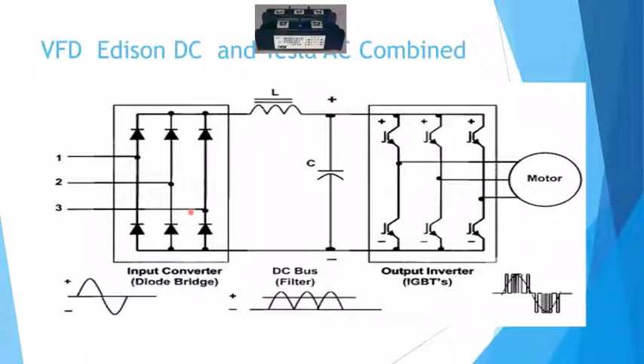Then what came about is the VFD technology. I was trained in this in the 80s very heavily. And what it's doing is basically have phase 1, phase 2, phase 3. You got your sine phase power here. It goes through diodes, and the first thing we're doing is building DC, which is what a lot of the original variable speed was, DC power, because you could vary the voltage and it would actually vary the speed. The DC goes directly on to the motor, but the motor has to be a DC motor with either permanent magnets, or it's got to have commutators in it, which basically allow it to shift the phases to get it to turn.